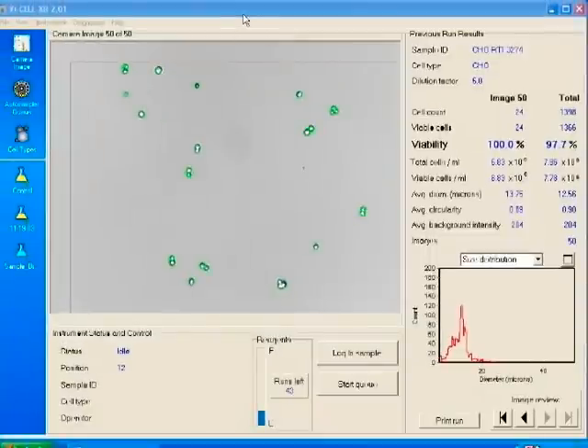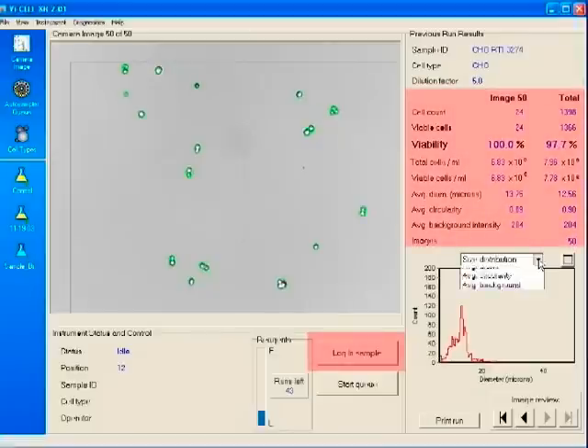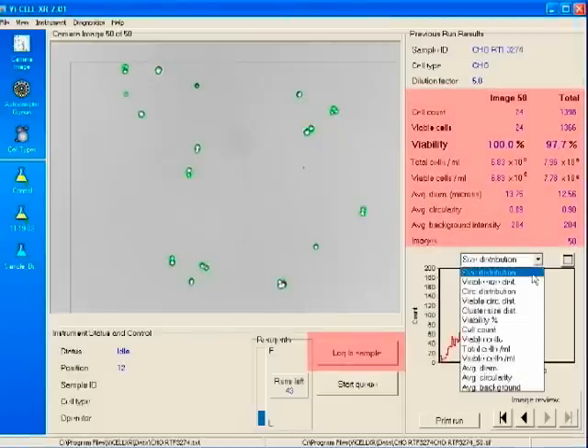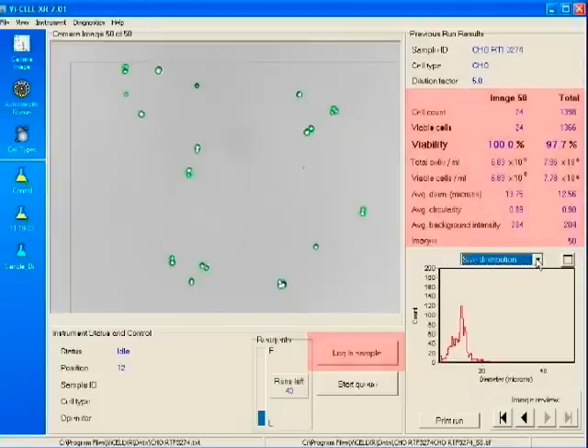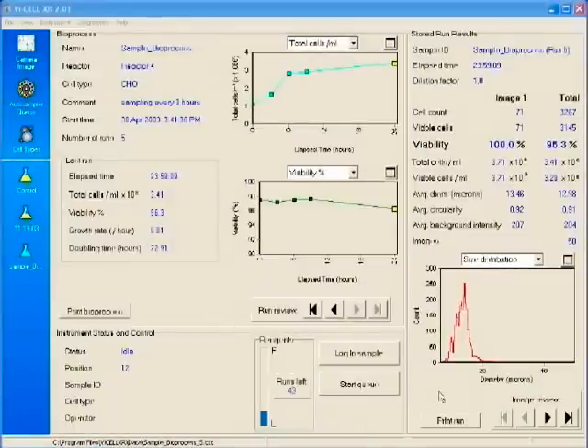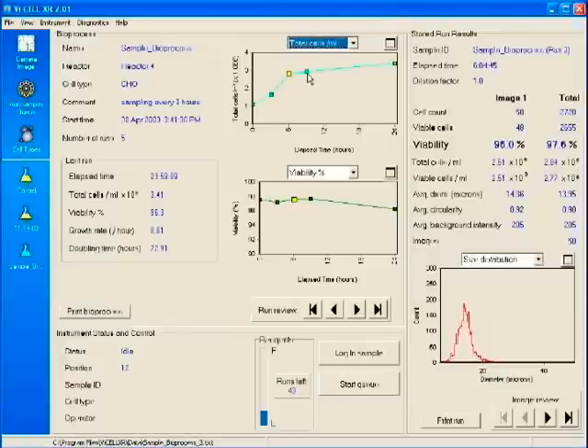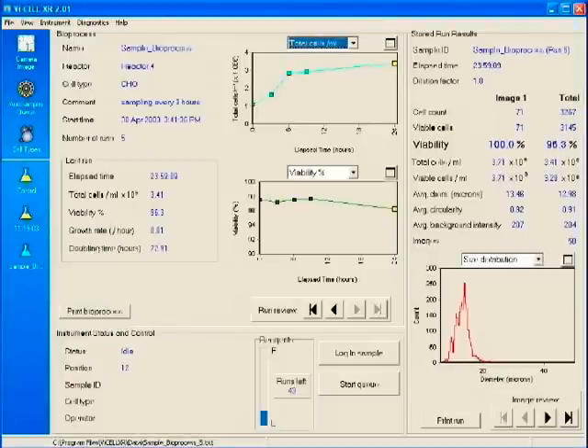The software program main screen, for many people, may be the only one they will ever use. Everything you need to log in samples and view results is right in front of you. All of the available graphs — such as viability percentage, viable size distribution, and total cells per milliliter — are quickly selectable via the drop-down menu. For the more demanding user, the time-saving Vi-CELL BioProcess feature allows automated tracking of cell culture parameters with respect to time, eliminating the cumbersome manual recording methods of the past.